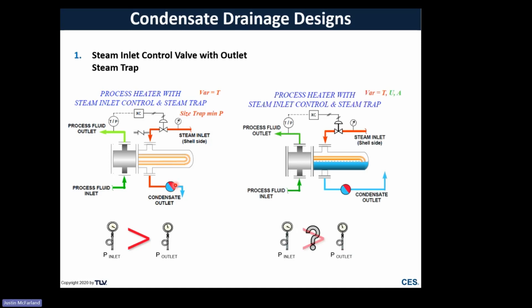As soon as we have a negative differential pressure, meaning that our pressure here is less than the pressure downstream, then what's going to happen is that condensate can't flow. And oftentimes there's a misconception thinking that, hey, I can just put on a bigger steam trap. Well, that's not exactly accurate. There might be some scenarios where that is helpful for sure, but if you have negative differential pressure, it doesn't matter how big of a trap you put on there, it's not going to flow. So inevitably you're going to end up backing up condensate.